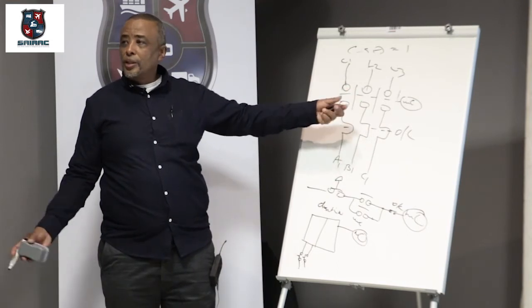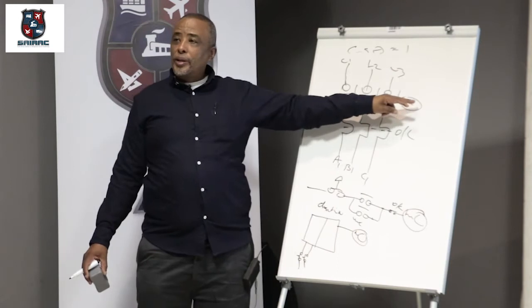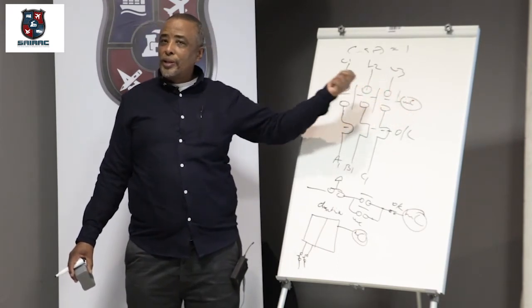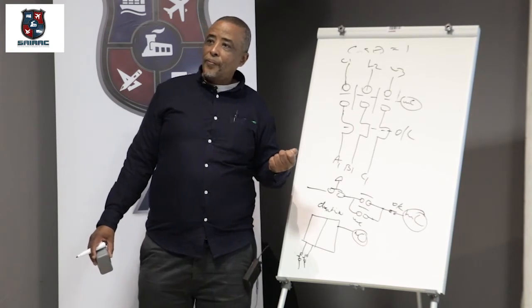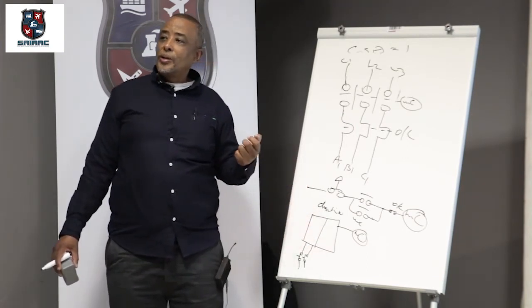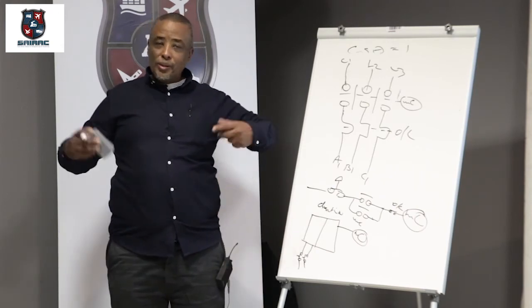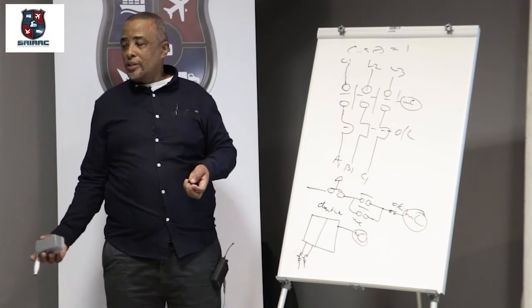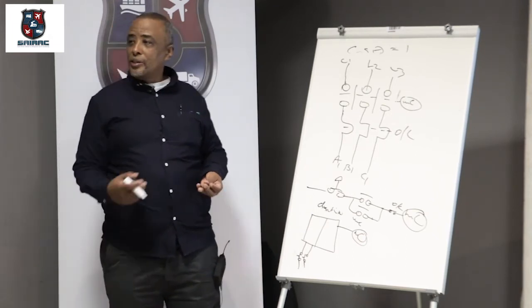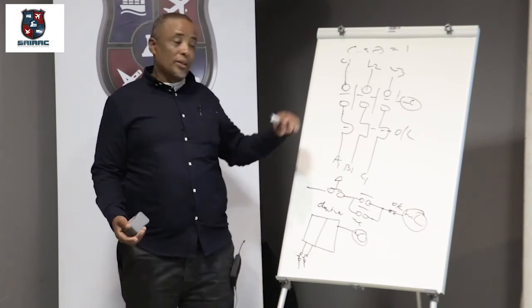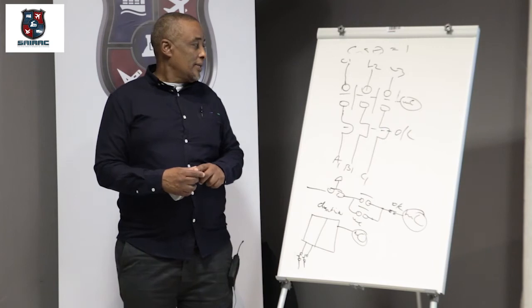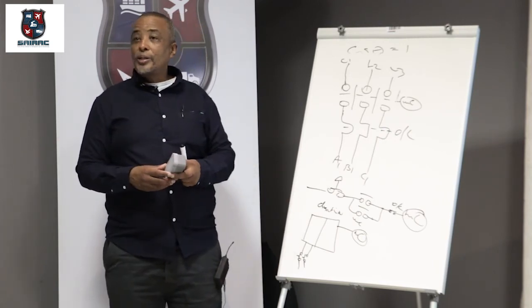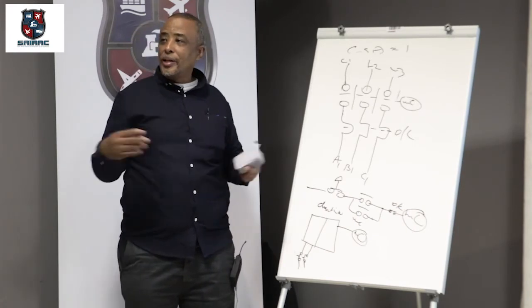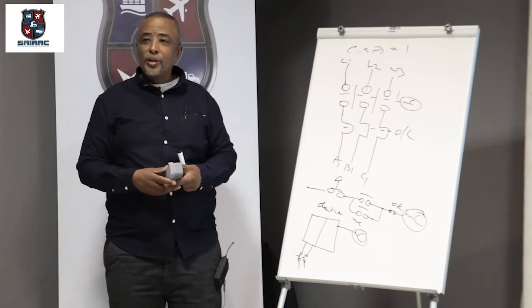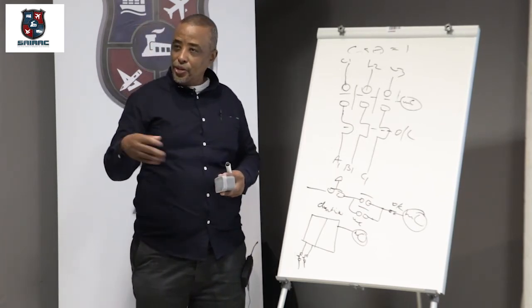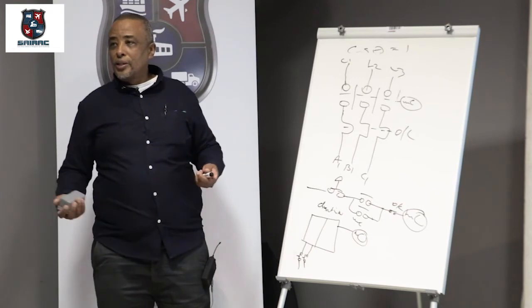Direct online starter, generally for smaller motors. You have a no-volt coil. The purpose of the no-volt coil is power failure. The coil will de-energize. The motor will not start up automatically until you press the start button, for obvious reasons. Think of a bandsaw, for instance. You're working in a factory, press the start button, the motor's running, and suddenly there's load shedding. The first thing the operator has to do is get a cloth, get a brush, start cleaning. They don't stand around talking about the weekend rugby or soccer, whatever it is. They clean their machines out. It's their time to do a bit of maintenance.